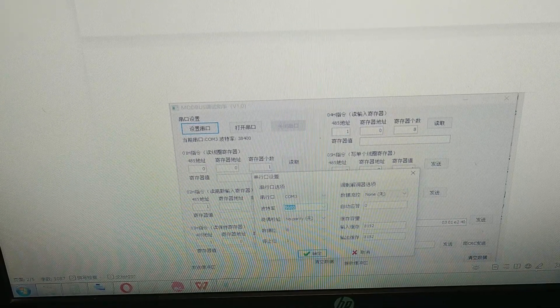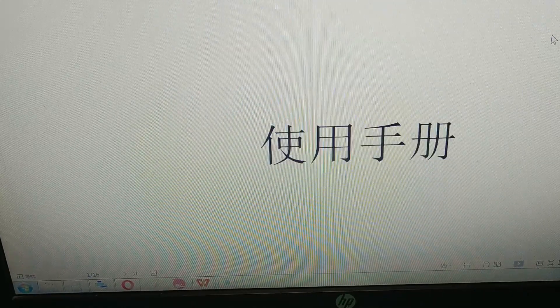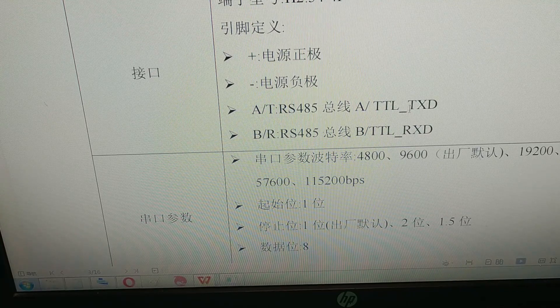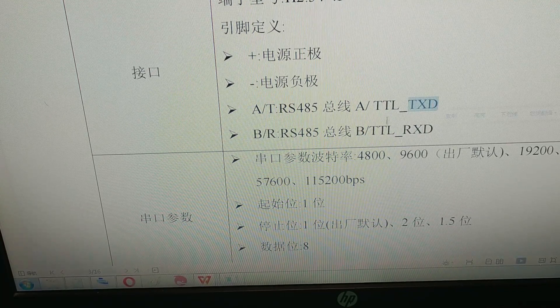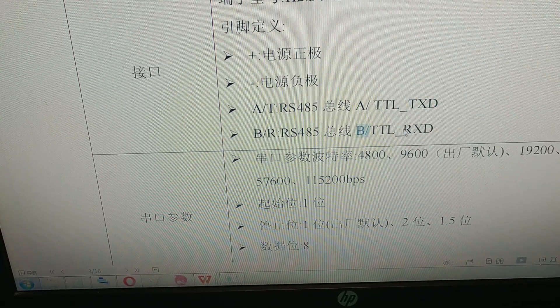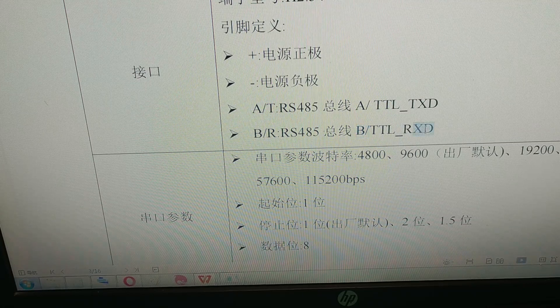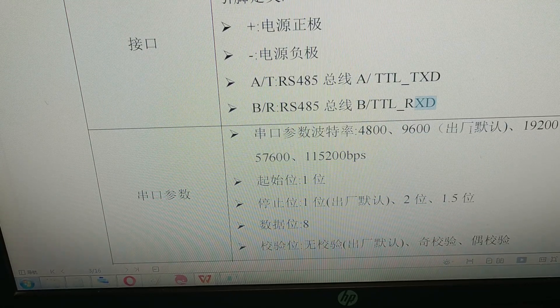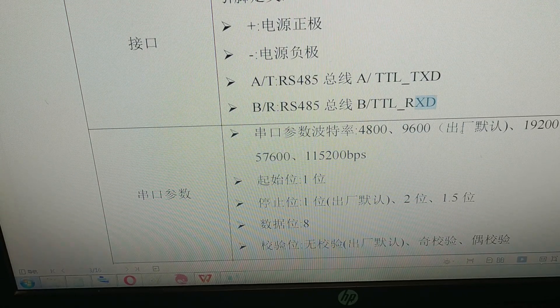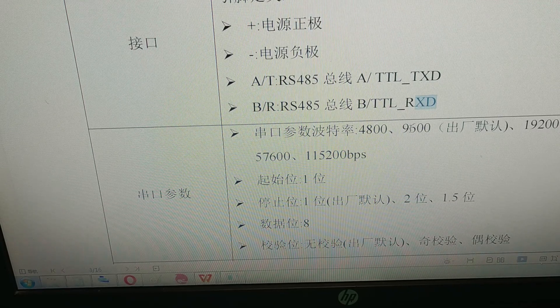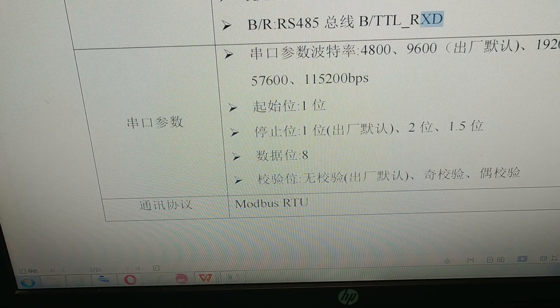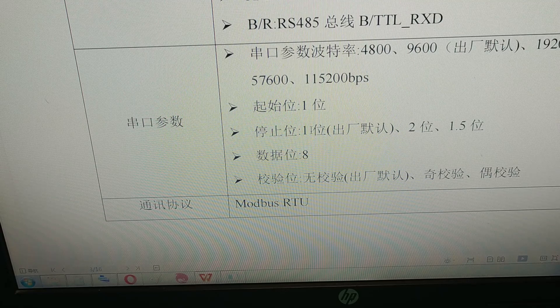Now how to use it? First of course we need to read the user manual. As you can see, A is associated with the transmit data and B is associated with the receive data port. The default baud rate is 9600, eight data bits and one stop bit.